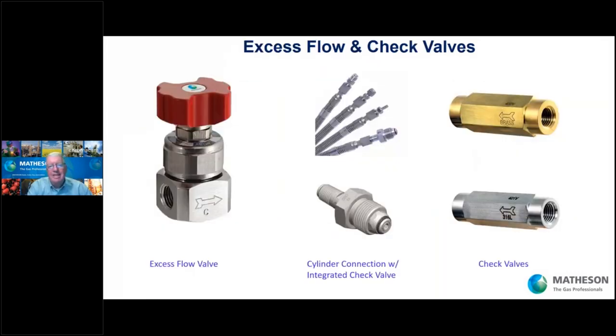Let's talk about safety-related valves. First, the excess flow valve. It doesn't require a controller, wires, or anything — it's a mechanical device. At a given pressure, if you have a flow higher than what should be occurring, this device will close the flow path. Gas goes through it, and until you fix that condition, it won't allow gas to flow. To reset it, you just use the knob. It's a very simple device but a very good safety feature to have in your system.